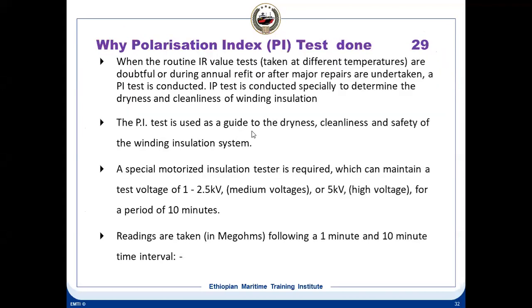There is another test called the polarization index test. This test is done only in the case of high voltage equipment, and when the routine IR values taken are doubtful. Suppose on a generator you just took an insulation resistance test and found that the values are conflicting, or sometimes you took two readings and they all differ, then you have to go for a polarization index test.